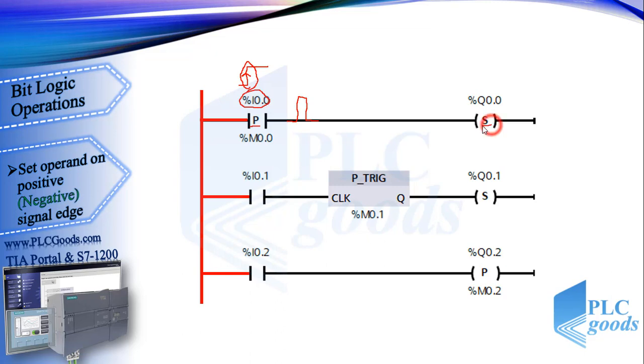Usually a set instruction is used to latch the state, so by the first line Q 0.0 remains on. If you use a simple assignment, Q 0.0 will be on for one program cycle which is about 5 ms. The next instruction is used to query a 0 to 1 change in the signal state of the RLO at its input.